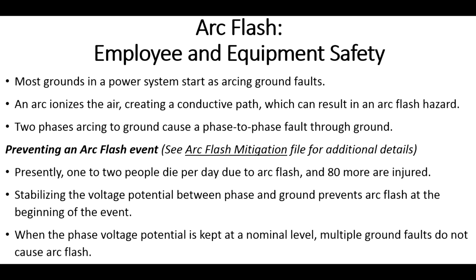If the voltage is stabilized between the phases and ground, arc flash can be prevented at the beginning of the event. So when the phase potential is kept nominal, multiple ground faults do not cause arc flash.